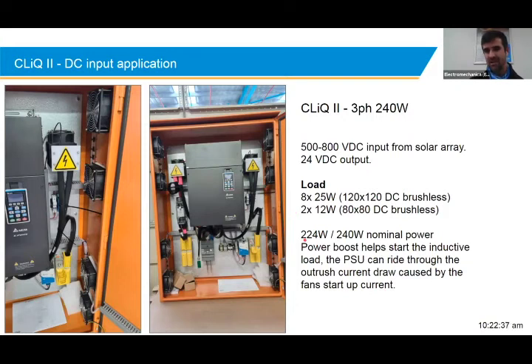at about roughly estimated at 224 watts at a 240 watt power supply. We're a little bit on the limit there, but what I want to highlight is that the CLIQ2, with its power boost function, is able to start these fans all together without any issue, as it can ride through that 150% boost for 5 seconds or more. So just an application where we have direct DC input and we need 24 volt DC output to these fans.